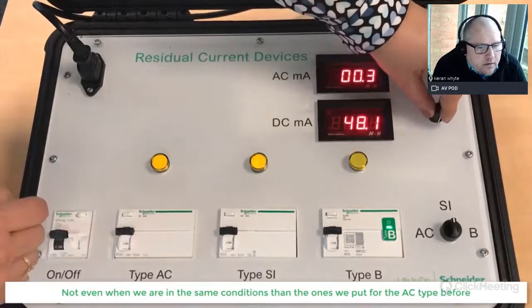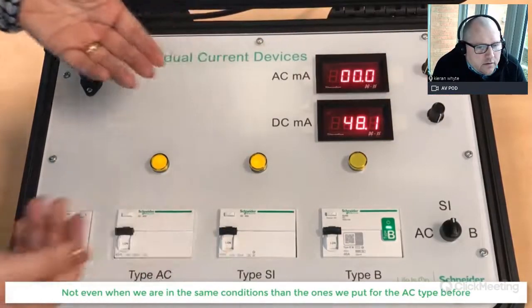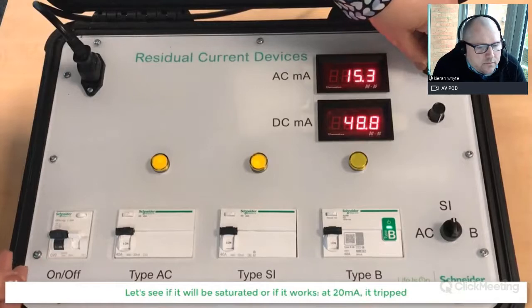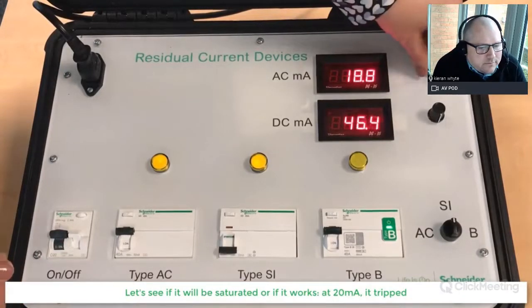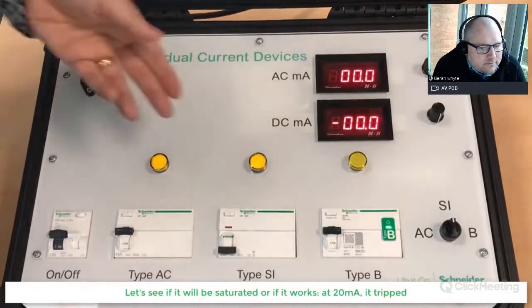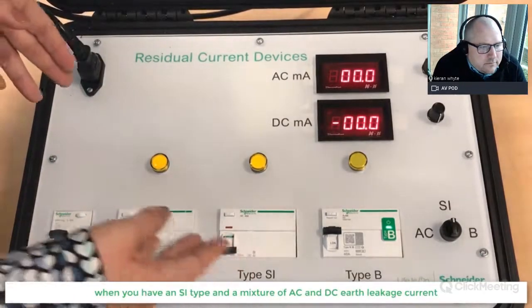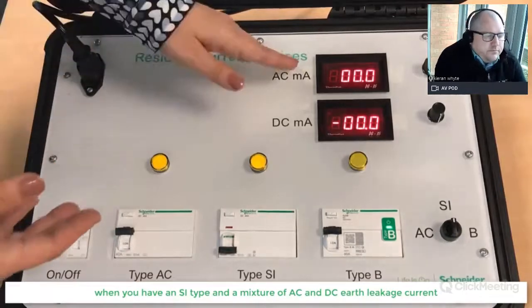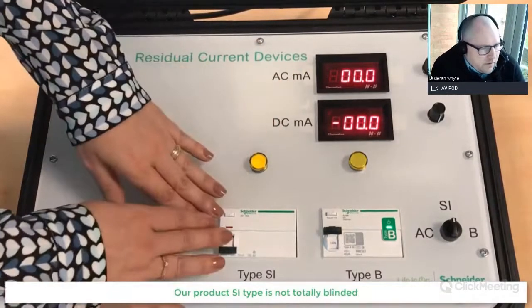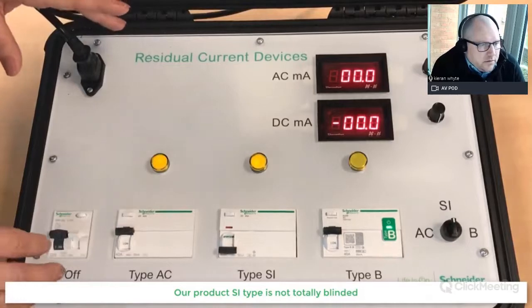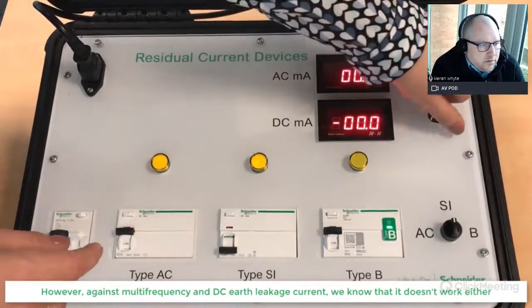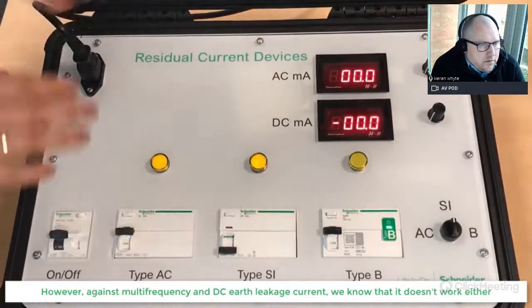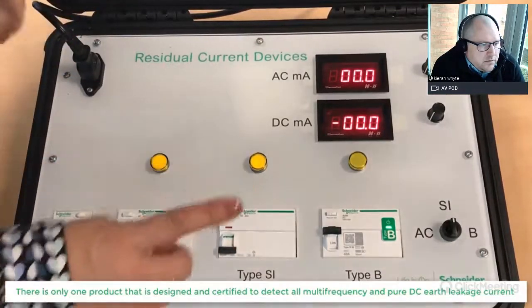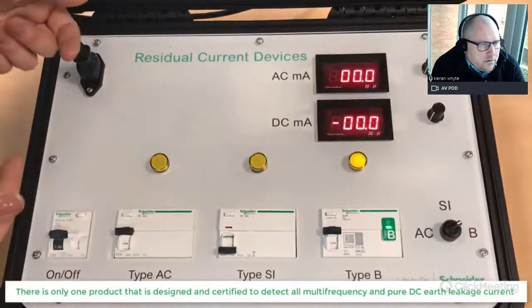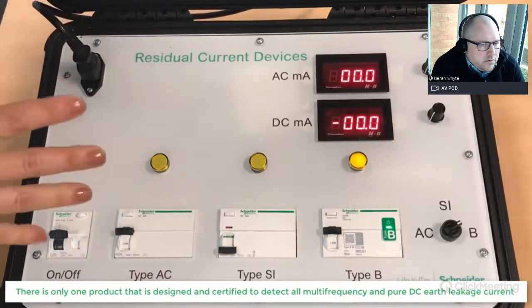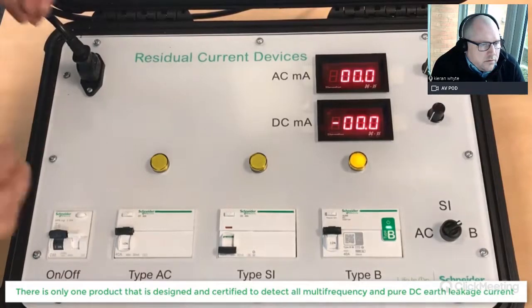Let's see what we did with the AC type before. Let's see if it gets saturated or if it works. You see we are at 18, and at 20 it tripped. So when you have an SI type and a mixture of AC and DC earth leakage current, our SI type product is not totally blinded. However, against some multi-frequencies and DC earth leakage current, we know that it doesn't work either. There is only one product that is designed and certified to detect all multi-frequencies and pure DC earth leakage current, and this is the B type.